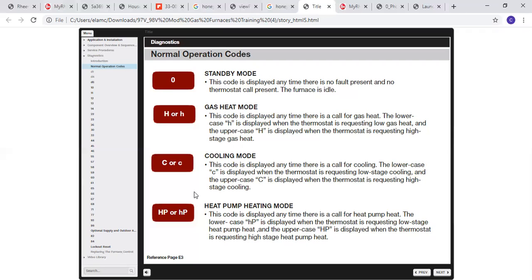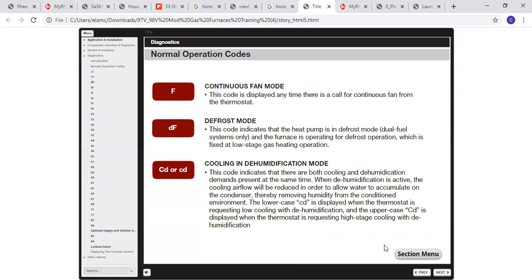And it will determine and indicate when it's in heat pump as well. So if you're in heat pump heating mode, it'll say capital HP or lowercase hp. If you're just in continuous fan, you will have an F. And if you are in defrost mode with a heat pump, you will see a DF on there. That indicates that you are in defrost mode. You also have a capital CD or lowercase cd. That's when cooling is taking place in dehumidification mode.